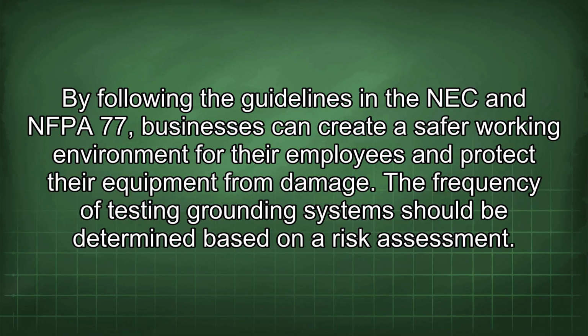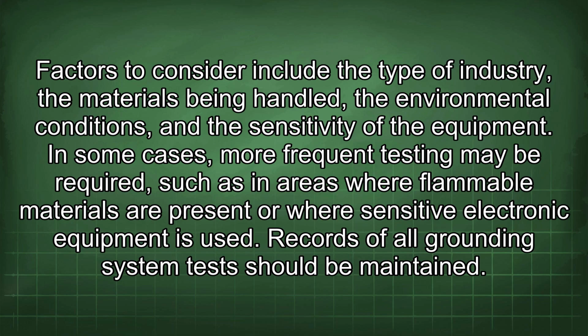The frequency of testing grounding systems should be determined based on a risk assessment. Factors to consider include the type of industry, the materials being handled, the environmental conditions, and the sensitivity of the equipment.